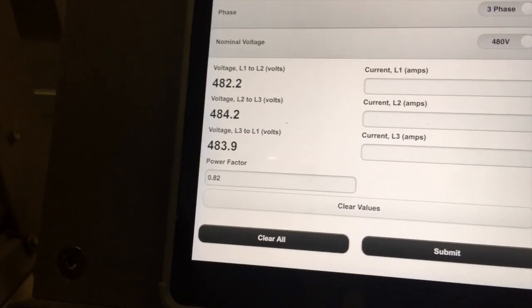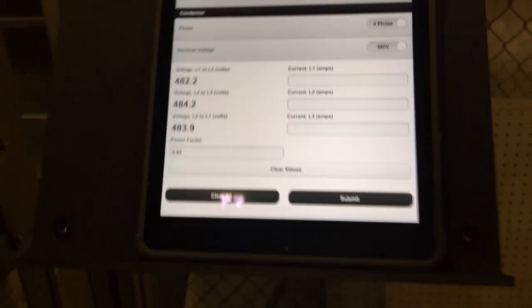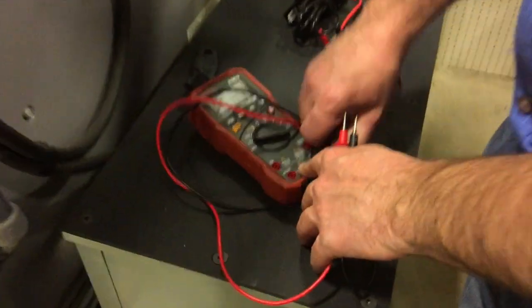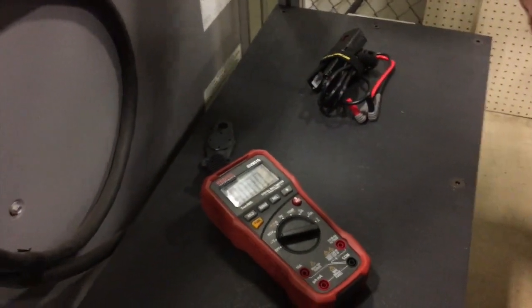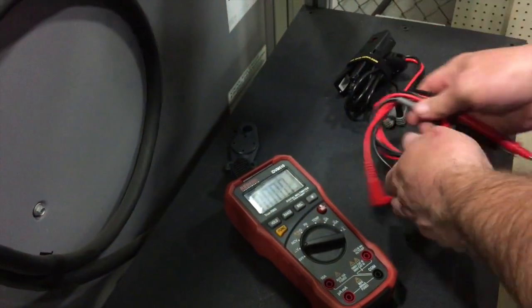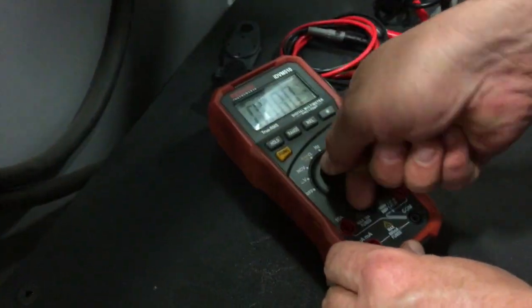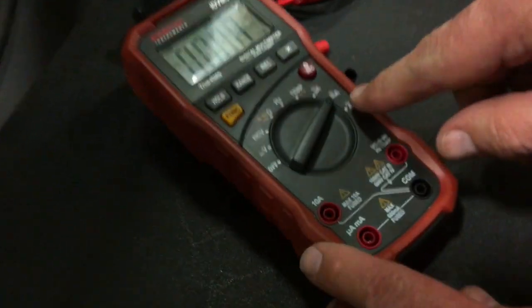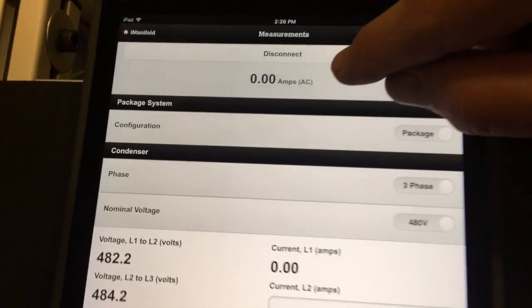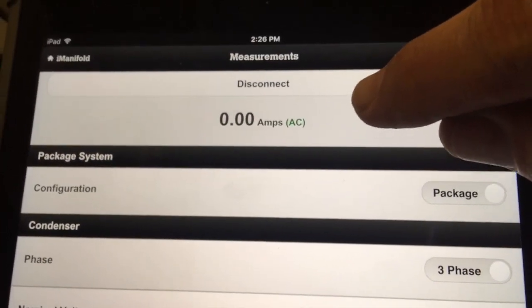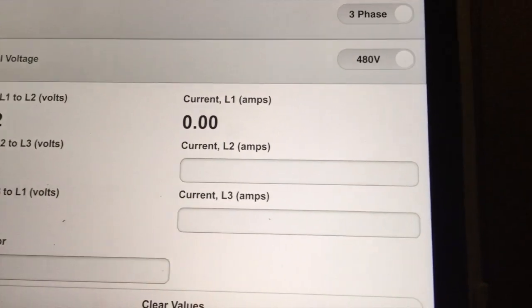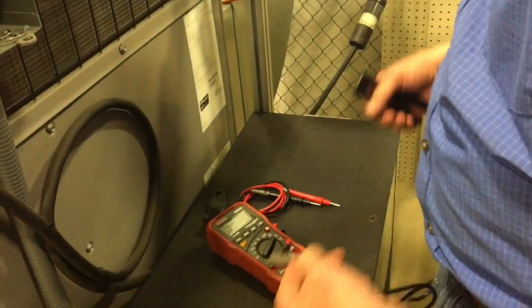And I have my 3 voltage readings. Now the next function here is I'm going to take the meter and we're going to switch over and read current. So I'm going to roll the leads up here, just get them out of the way. And I want you to notice something on the application. As soon as I turn the meter here to milliamps and again push the function key, the application automatically determined that the meter was set to amps, set it to AC, and it went to the first current measurement. Again, no interaction with the electrical meter required, aside from getting it set up properly.